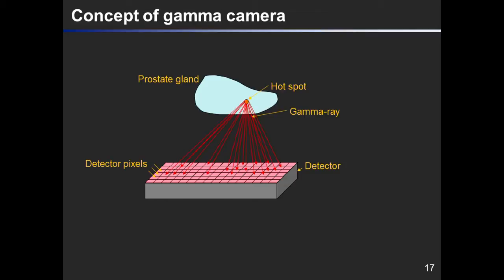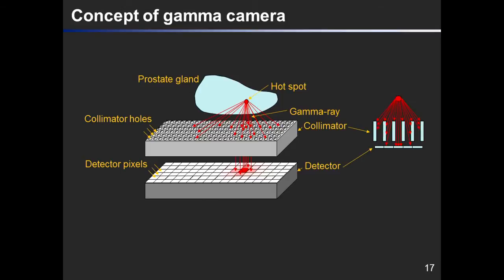So basically, we just get a flat image. So we need something between them that will be a collimator. A collimator is a high-density material with many parallel holes in it. It's the most simple design. So this is a cross-section of the collimator. We can see when the hotspots emit gamma rays, for the one hole right underneath the hotspots, all the gamma rays go into this hole, go through it, and are detected by a pixel.